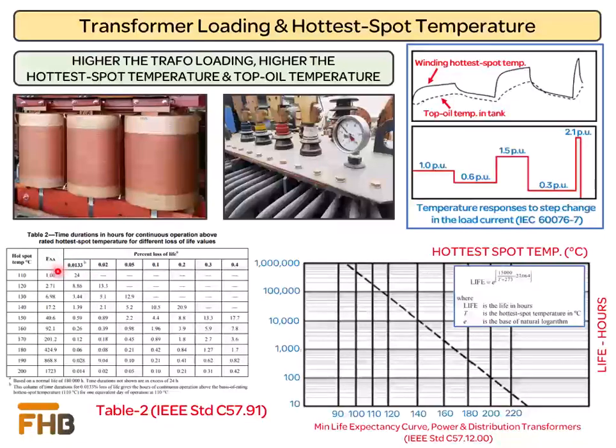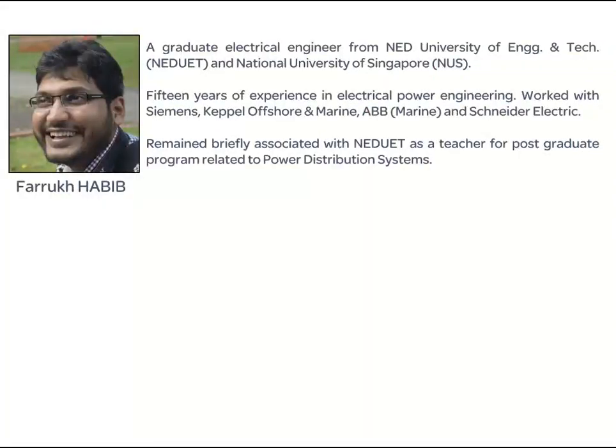However, if the same transformer is operated at a higher temperature, the same loss of life will occur in less operation time. If the transformer is operated at a temperature higher than 110 degrees centigrade, then the loss of life is further accelerated. From today's discussion, we can conclude that the loading of the transformer is purely dependent on its hotspot temperature limit, and the hotspot temperature limit is dependent on the ambient temperature and the winding temperature. If the hotspot temperature of the transformer increases from the design value, then we will compromise the design life of the transformer. So this is the end of our today's video.